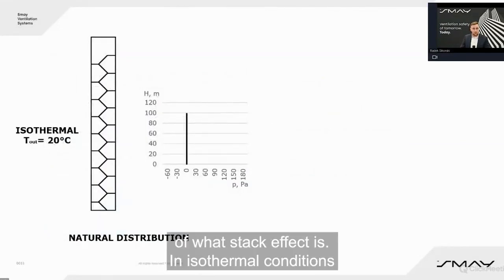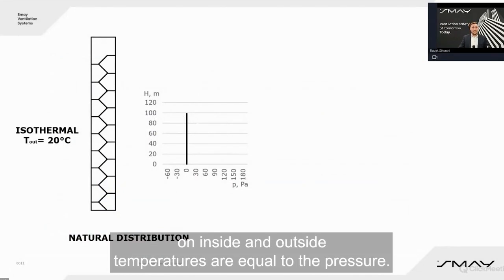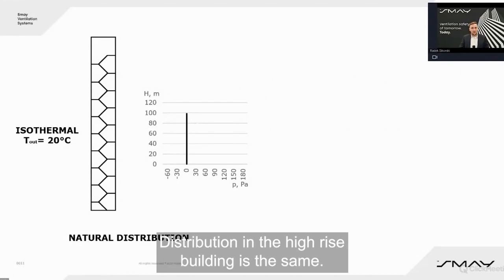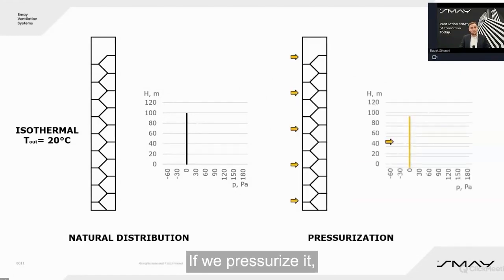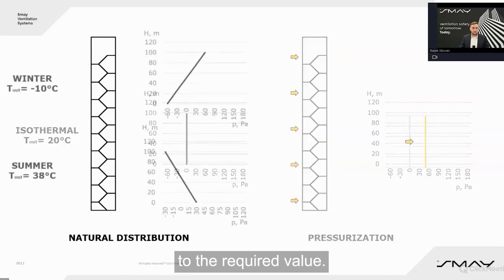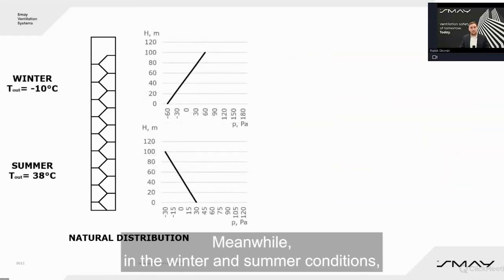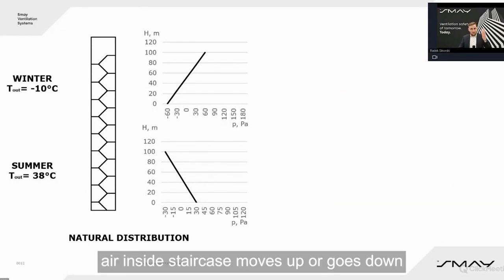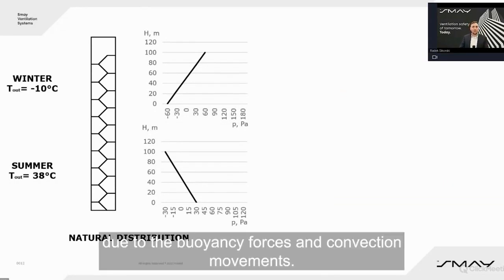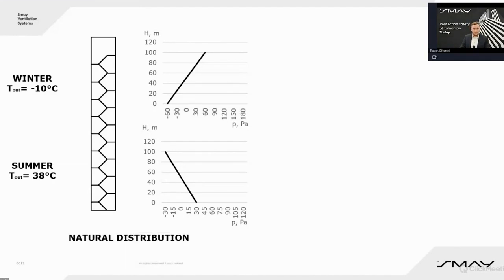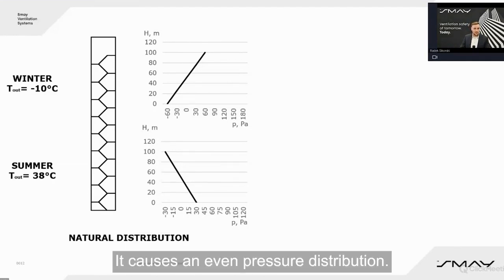A quick reminder of what the stack effect is. In isothermal conditions, so when inside and outside temperatures are equal, the pressure distribution in a high-rise building is the same. But during winter and summer conditions, air inside the staircase moves up or goes down due to buoyancy forces and convection movements, causing uneven pressure distribution.